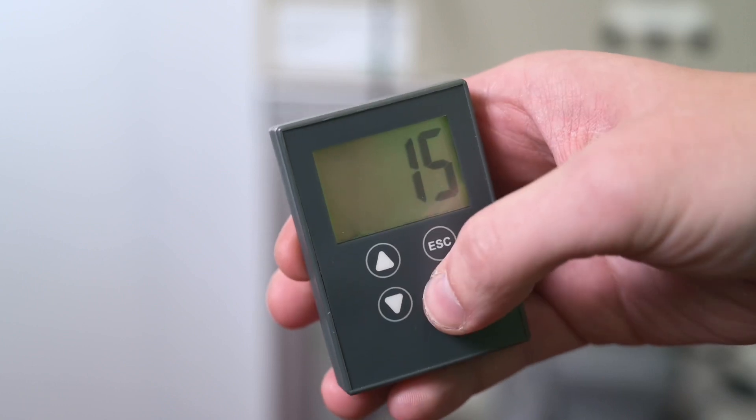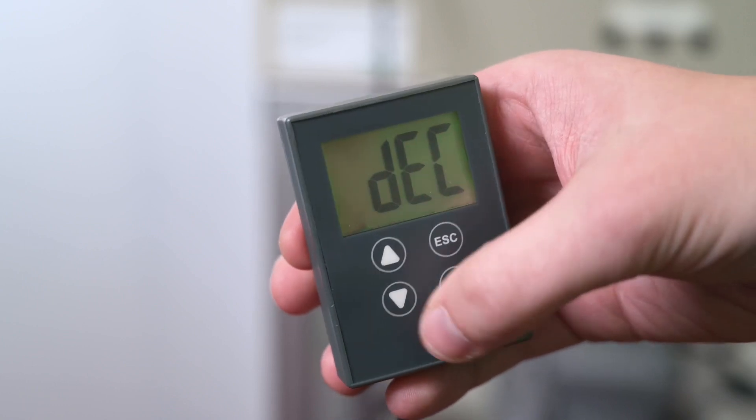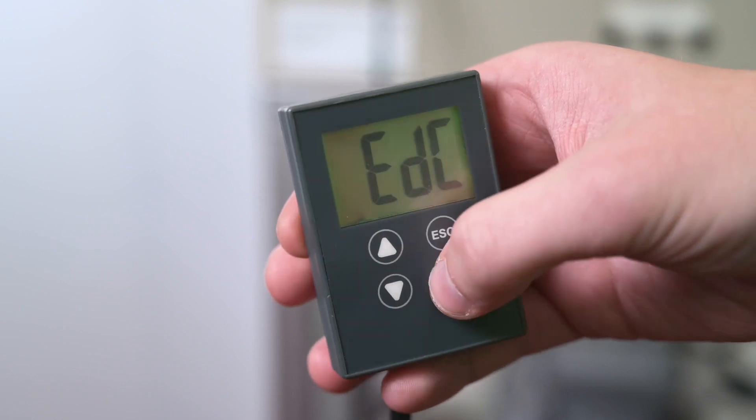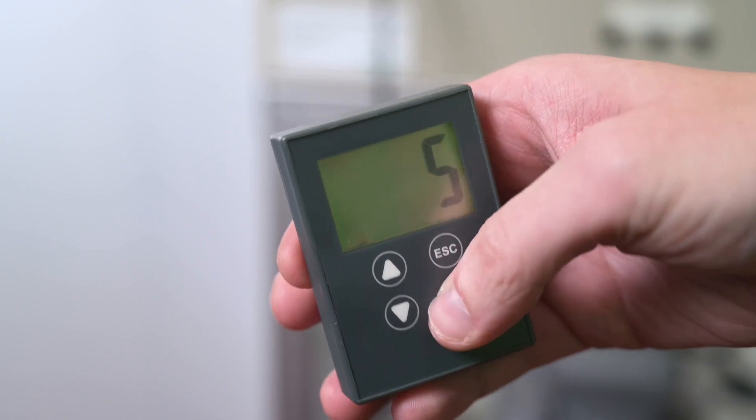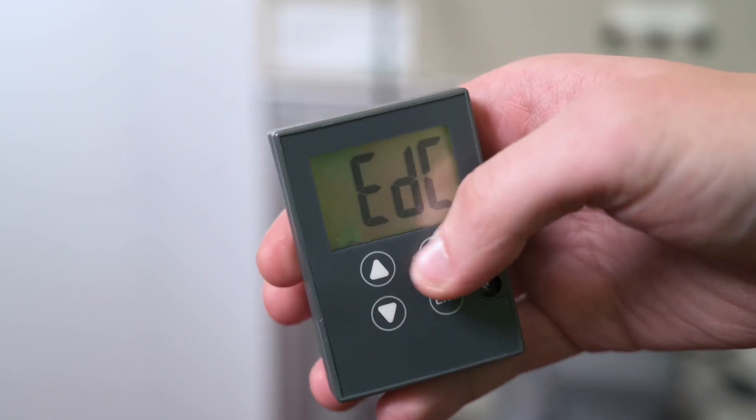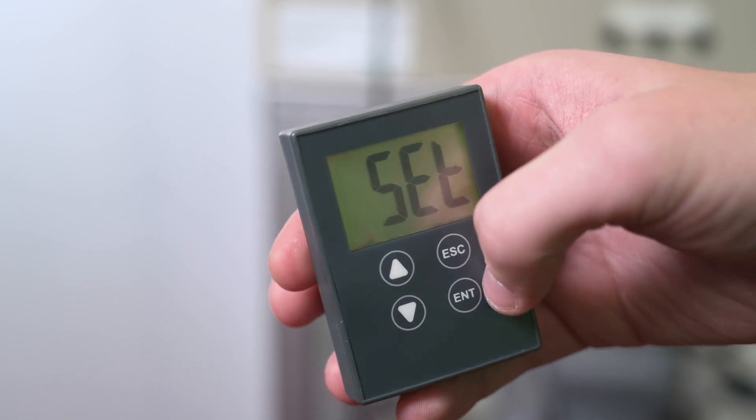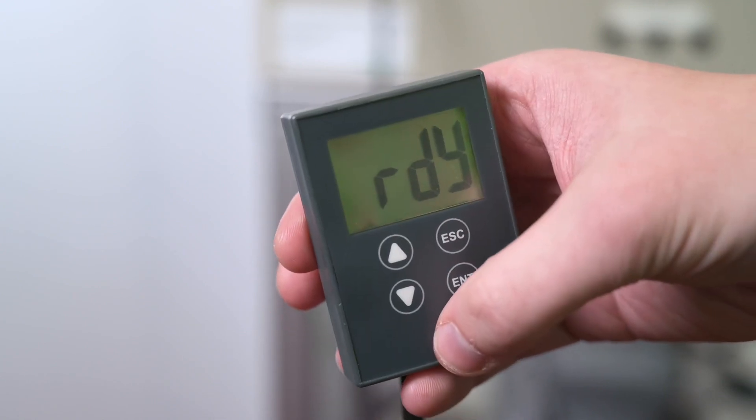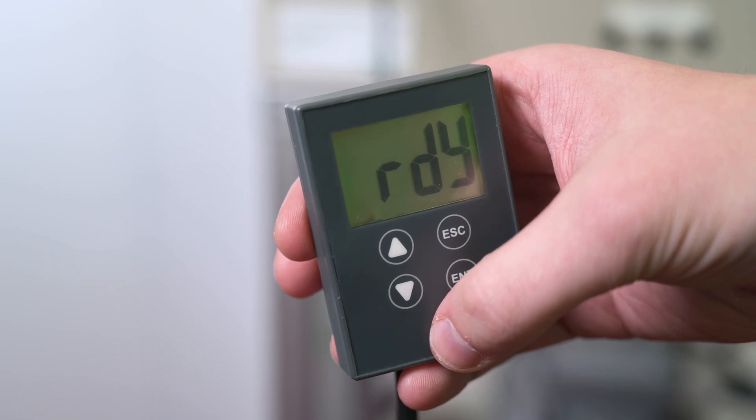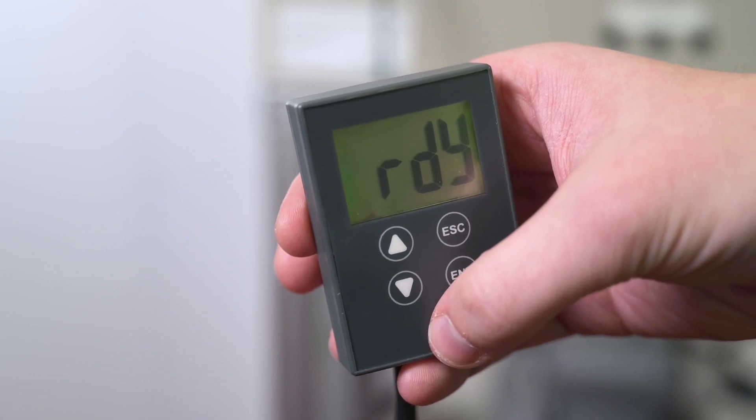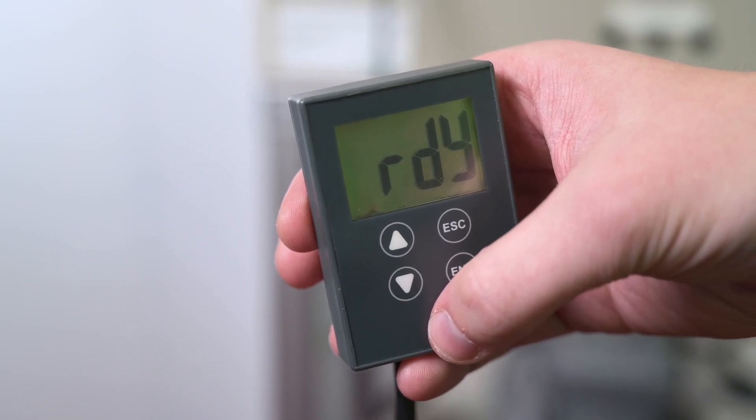This parameter is usable only for pump applications. With the parameter EDC, it is also possible to define a threshold for switching from controlled torque to freewheel stop mode. Like for the soft stopping by torque control, this parameter is only available when STY equals D.